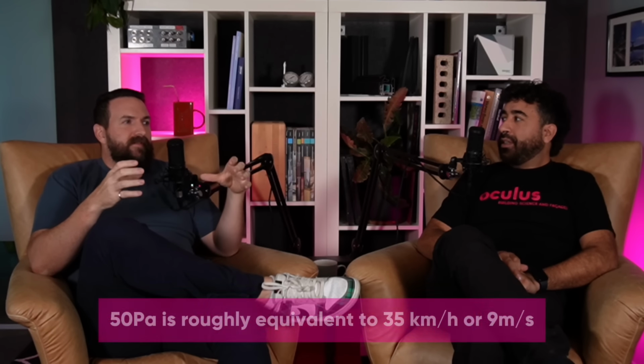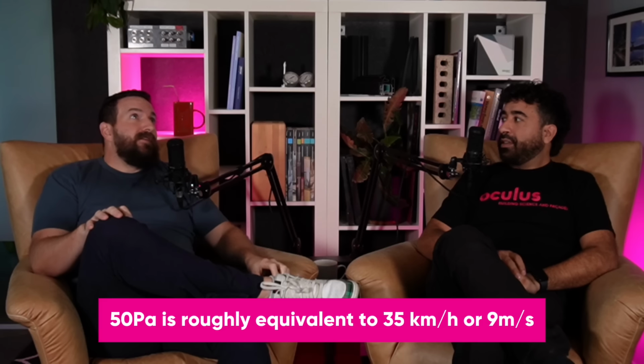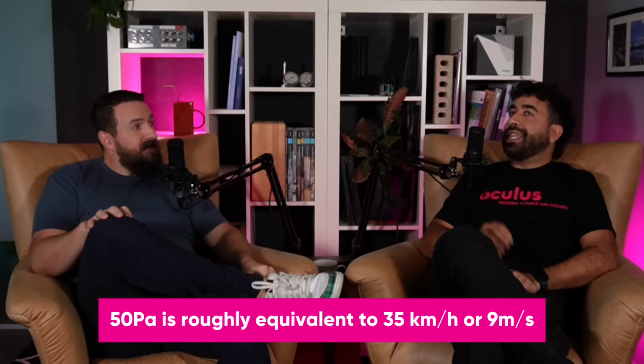Yeah. 50 pascals is like, I think it's 35 kilometers per hour. And that's constant pressure. Constant pressure, yeah. And you're right, around houses it's very complex how air moves. But back in probably the 70s, 80s, Brands did some work on this, trying to correlate the test conditions to in-service conditions and used tracer gas to do this comparison. Long story short, if you didn't have anything else to go by, divide by 20 would get your natural air infiltration through the enclosure. Which you can pretty quickly figure out is not going to be enough to ventilate your house.